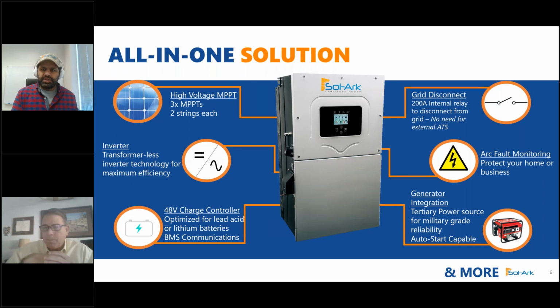You have a load disconnect for the grid input. Now, what this means here is a grid disconnect. Actually, you would still need an external disconnect as your service disconnect, essentially, for the inverter, your PV disconnect. But internally, there's a mechanical relay, so there's no need for an ATS. As David pointed out in an earlier slide, the 5 millisecond UPS time. We're able to do that because we don't use an external automatic transfer switch. Here, the Sol-Ark is connected to the grid, and when the grid goes out of parameter and we need to disconnect from it, as per UL 1741, we open this relay and we're no longer connected to the grid. And in 5 milliseconds, we can start discharging the batteries and diverting PV power to the loads immediately without need for an external ATS. Arc fault monitoring is built in, ground fault detection is built in for PV side.